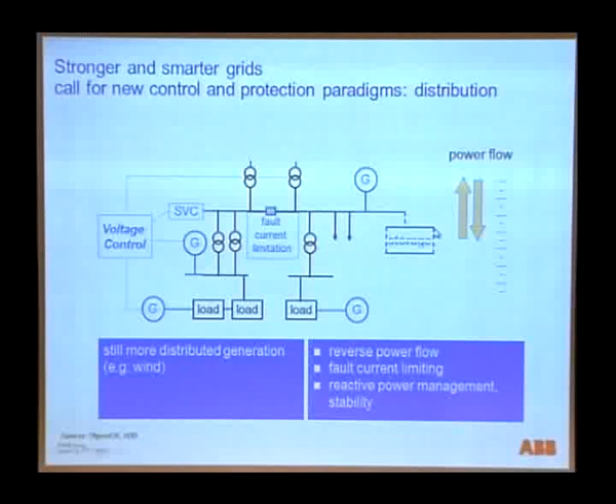As you still add more generation, at some point you reverse the power flow. So it'll be a distribution and collection grid combined, which raises the next challenges of dealing with fault currents and reactive power. So there's more control to be done here.